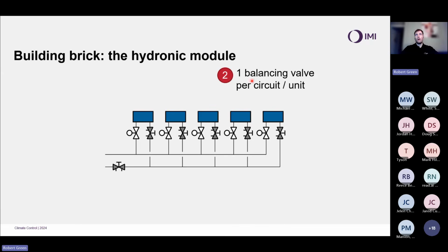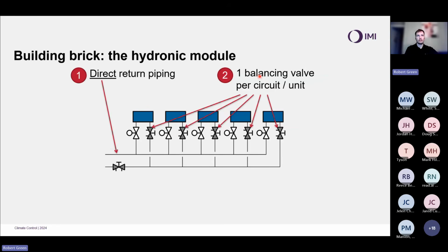We want to have one balancing valve per circuit or unit. Pretty simple and straightforward. We want to measure the flow on all of my fan coils or my air handling units or whatever these devices are. So we're going to want to put a balancing valve on there. Nice and easy. We also need to use something called direct return piping. Direct return piping means we flow into the unit and directly return back. And this is really important if we want to proportionally balance.